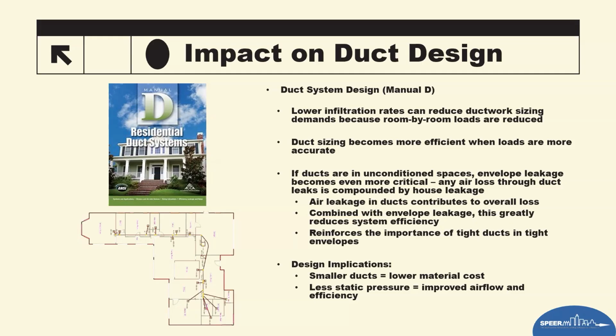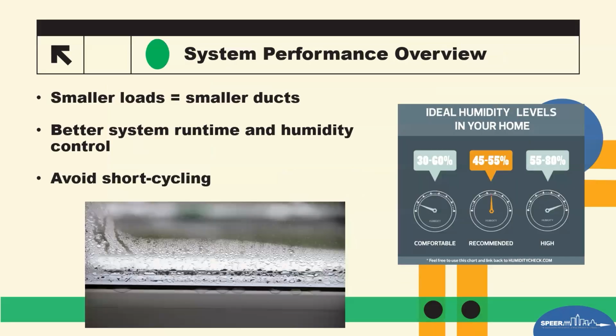But today's HVAC systems are not cheap. They should all be installed per the manufacturer's installation instructions to achieve the highest possible performance and longest life of the equipment. There's something out there now. We went through it on a few webinars ago: HVAC grading. What you're doing is just verifying that it is A, installed per the manufacturer's instructions, and B, the performance is at its peak efficiency so that it can actually run to its best performance to be able to condition the home and have better comfort for the occupants and do humidity control as well.